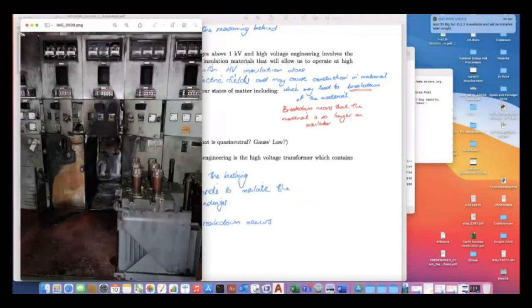This is an example of the consequence of an oil type circuit breaker not operating correctly. Basically, oil is in a container, this enclosure here, and then two electrodes move apart in the oil. If it doesn't operate properly, an arc will form, it'll generate heat, it'll generate gases in the oil, it'll explode, and you'll basically cause a fire. This will then damage all the other components in a switchgear room or a substation.